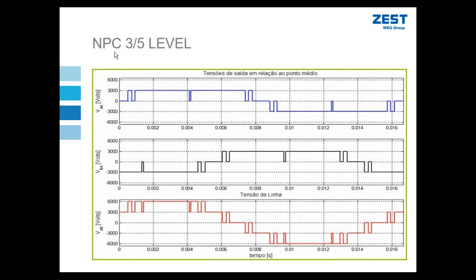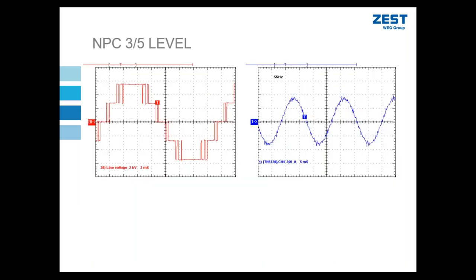So this is called an NPC three level topology, because in the phase to neutral voltage scenario, I have positive DC link voltage when I'm switching my two upper IGBTs, or I have zero when I'm switching my two inside IGBTs. So that's my second level. And then my third level is when I'm switching my outside two, bottom two IGBTs, I have maximum negative DC link voltage. And that's where my three levels come from. But when I combine these two, I actually get a five level voltage waveform to the motor. So if we look here at the voltage A to B, I have 6,000 volt, 3,000 volt, 0 volt, minus 3,000, minus 6,000. That's five levels. And that's just an actual measurement of it.